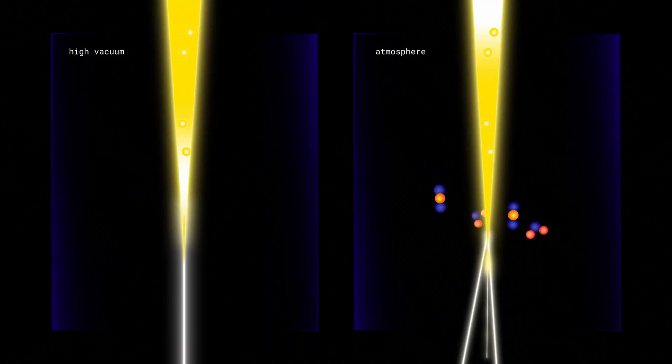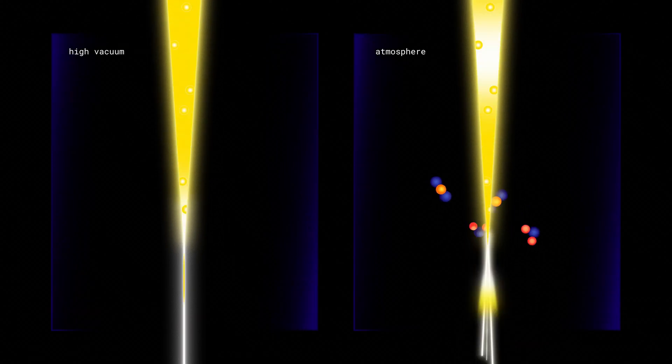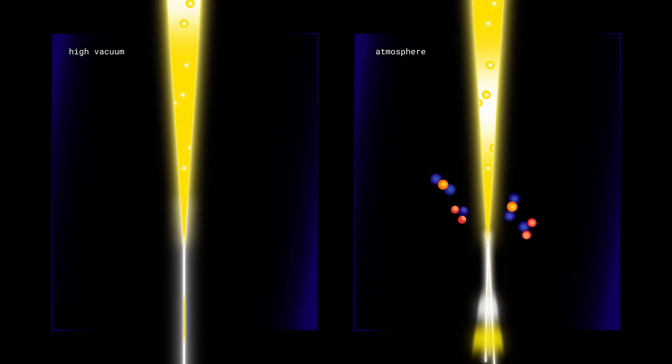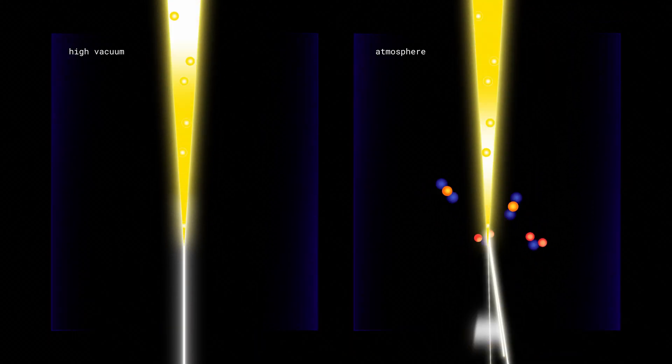This is important as scattering or attenuation of electron beam will increase the spot size of the beam and reduce resolution, especially in the secondary electron mode. The high vacuum condition also optimizes collection efficiency of the secondary electrons.